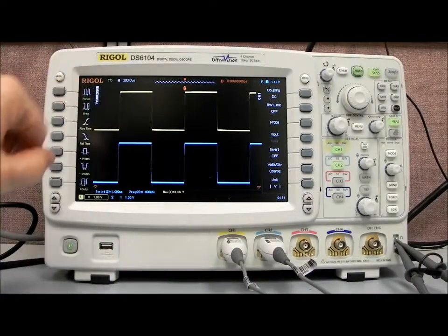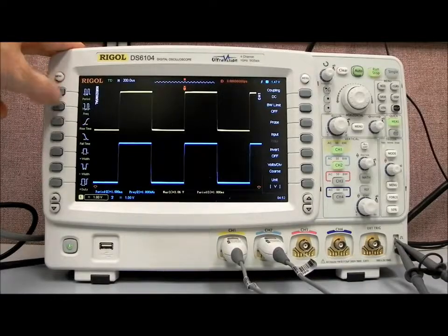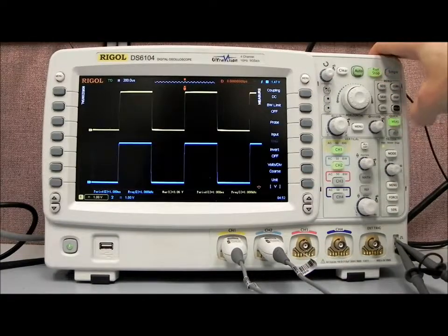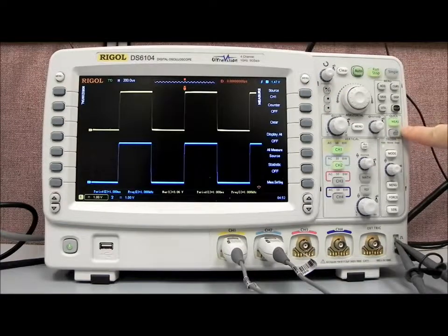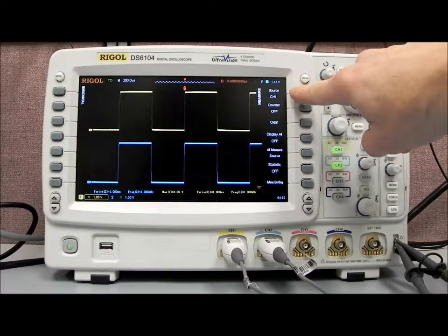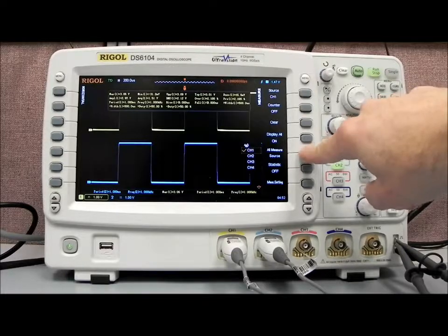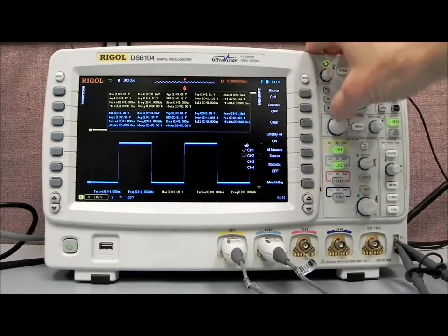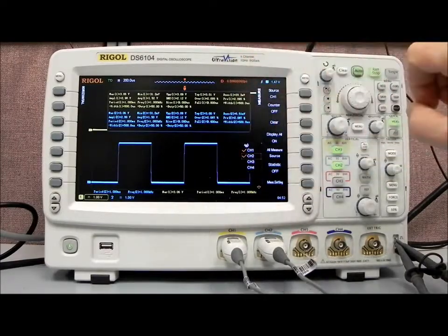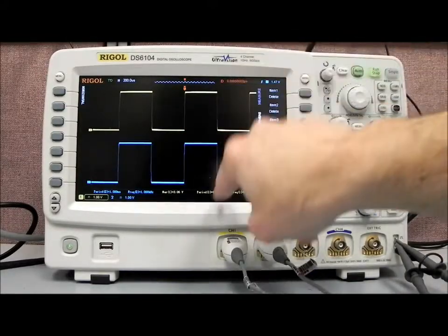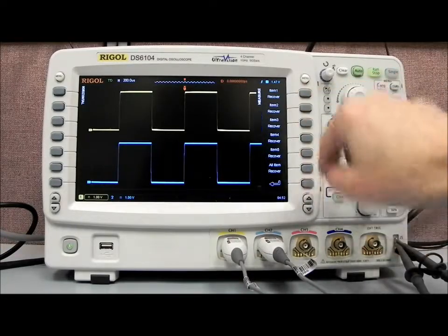If we press the menu key again, we'll see the horizontal menu will come up, and we can select period. Again, here's the period, here's frequency. And so let's say we wanted to do some more with our measurements. In the menu over on the right hand side, we can see that the measurements are located in this area. We can select which channel we're going to be working with. We can display all, and that will display all for that channel. And we can also select channel 2, and now we'll have all of that data as well. Starts to get pretty filled with data if you'd like, and then very easily we can do display all off and it will clear it. We can also clear all of the items here by selecting delete all, and we're all set.